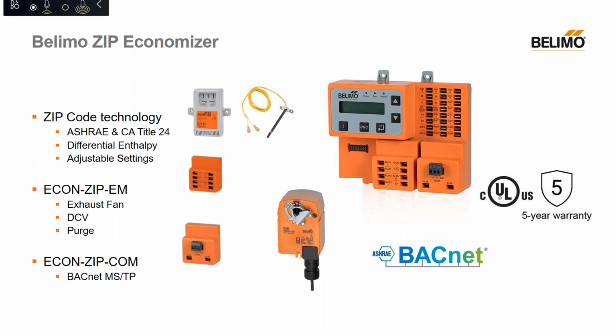So for instance, you might want to consider using a differential enthalpy strategy. So you're looking at relative humidity at both the outside air and return air side of your rooftop unit. Once you plug in two Econ Zip temperature humidity sensors and the Econ Zip 10K sensor to your supply air temperature, it will know that you're using differential enthalpy and you don't have to go through the settings to change it to that strategy. Also, you can manually adjust if needed or desired for your facility.